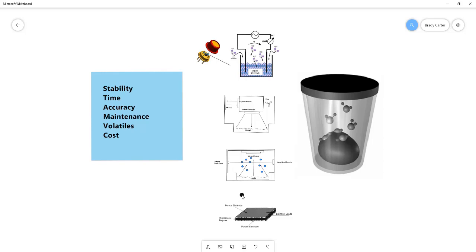Now, when we talk about accuracy, of course, we're talking about whether or not the right value is measured, versus precision, which means do you get the same answer every time? And really, this can only be measured on specific samples because you have to know the water activity. And so there are both saturated salt solutions and unsaturated salt solutions available for doing these measurements. And the accuracy and precision that's reported is always measured on these types of samples under ideal conditions.